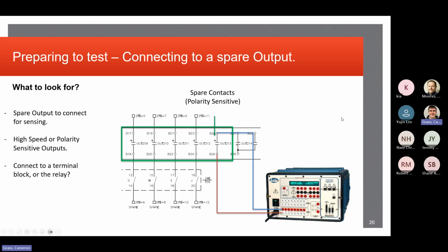Continuing on, one of the things that we do to verify the relay's functionality based on the settings is we usually connect a spare output from the relay, something that's not connected to terminal blocks, if we can. Something that's usually just labeled as spare in the relay settings. That's what we plug into for the logic input to basically change the parameters of that output. In this case, for the example here, it would be out 213. We'd basically be changing the output parameters to verify testing points. So if you're testing a certain element, you'd place that element within out 213 so that the output would operate when it needs to. Again, it's all based on what you're testing at the time, but that's usually how we do it to verify it. And again, this is what we would be pulling for the SER data to supply to the client in this case.